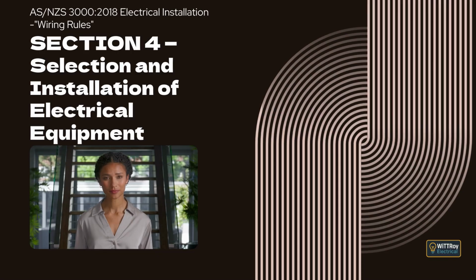Clause 4.2.2.6 Prevention of spread of fire. This clause explains that switches, socket outlets, and similar accessories must be arranged so there is sufficient separation from openings in fire-rated walls, ceilings, or floors, and that openings made for electrical equipment must not weaken fire-rated barriers beyond the permitted extent. Clause 4.2.2.7, Thermal insulation, New Zealand only. This clause explains that in New Zealand domestic installations, appliances and accessories must not be installed on thermal insulation in ceilings, walls, or underfloors, and this applies even if insulation is not present at the time but may be added later.